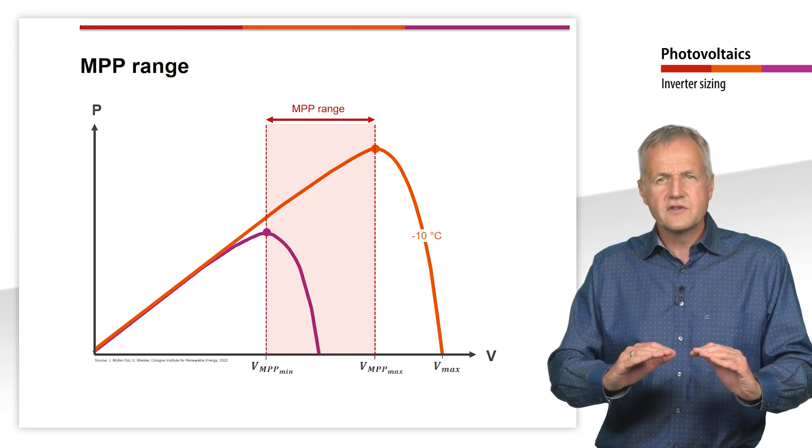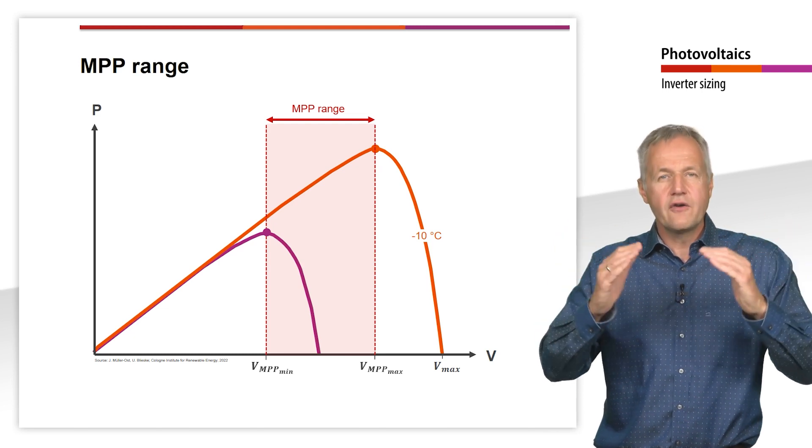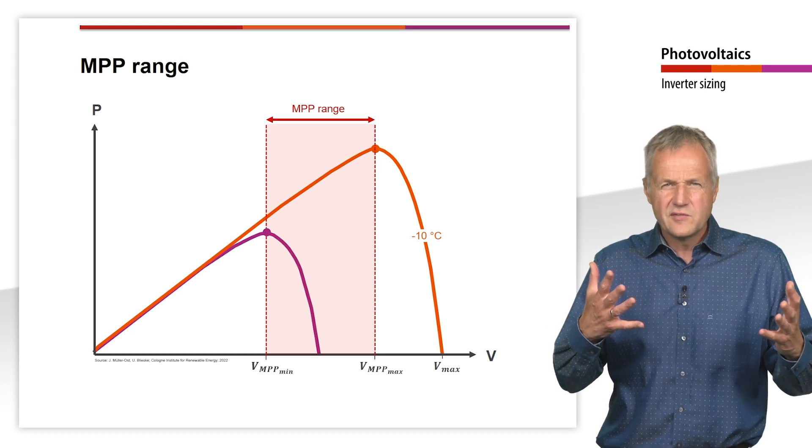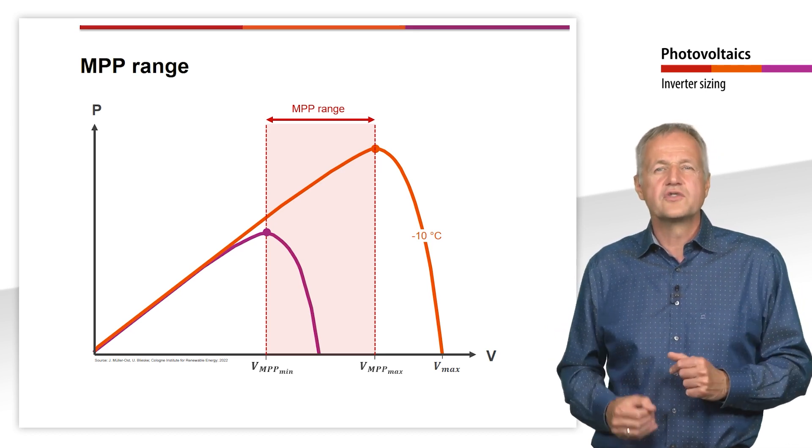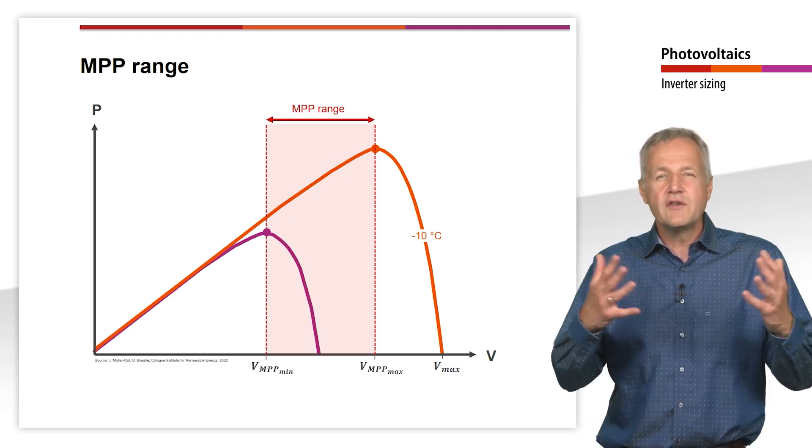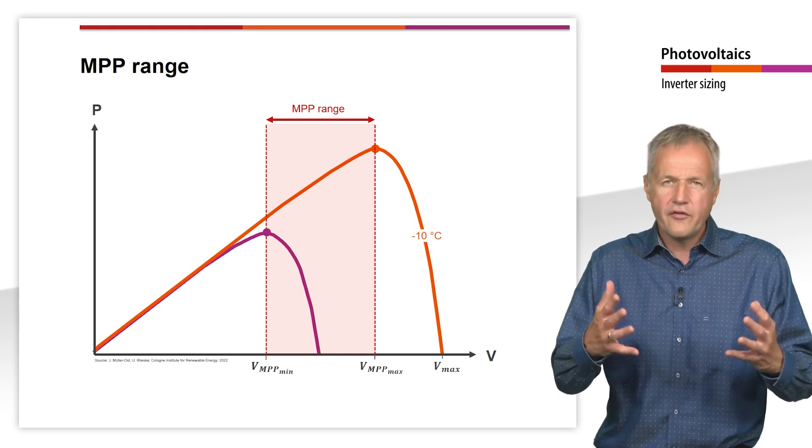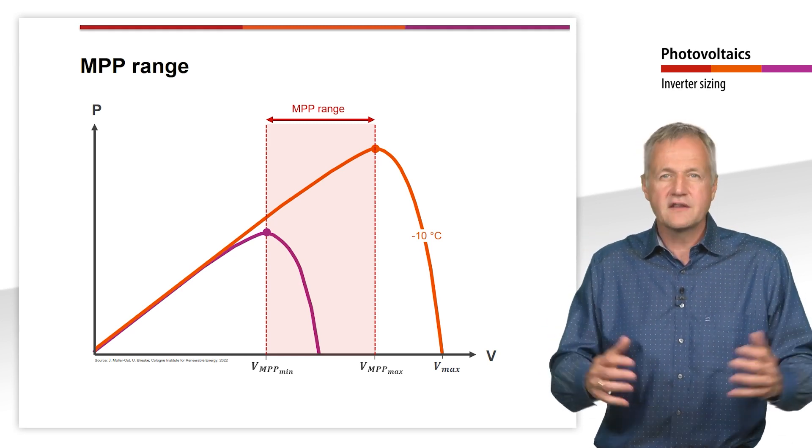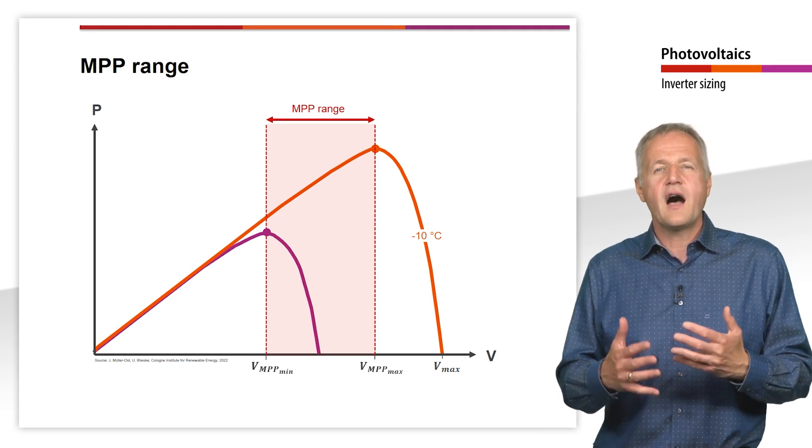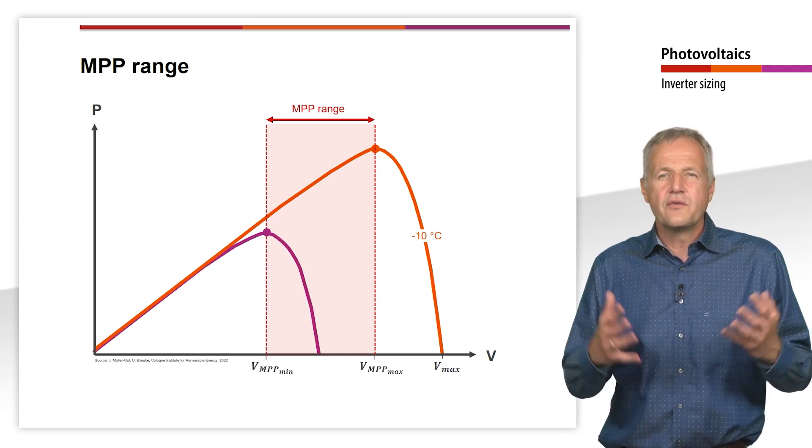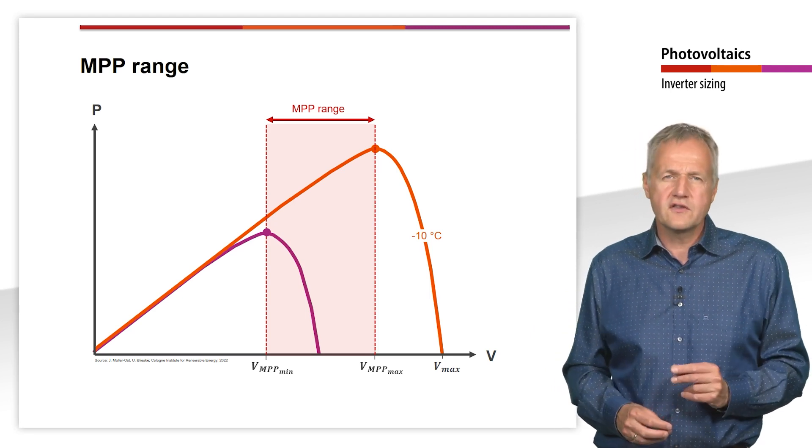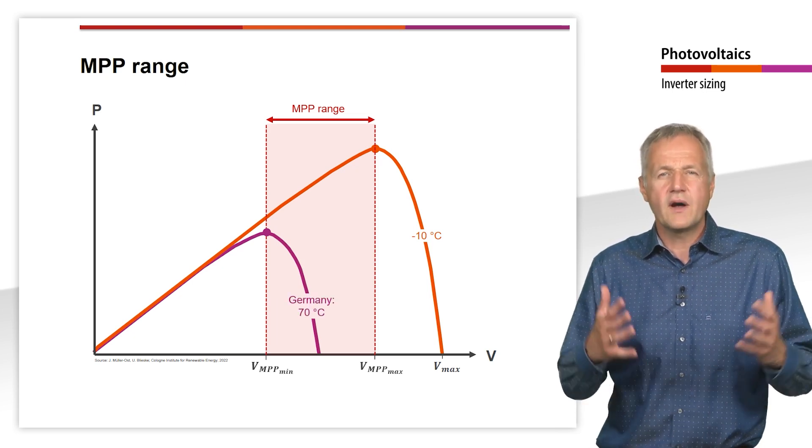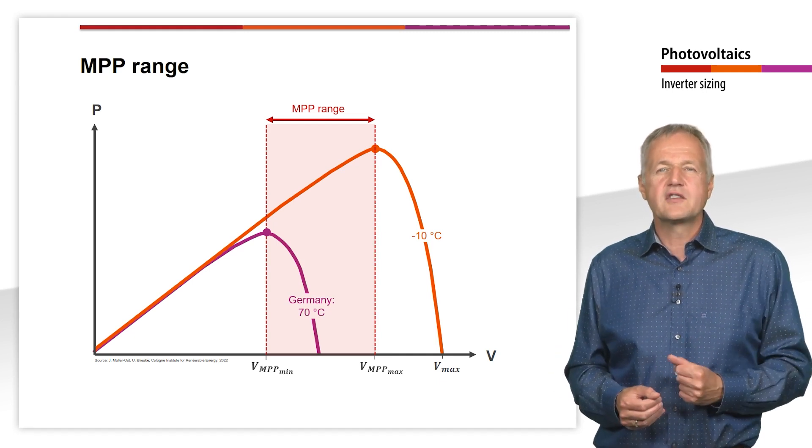This occurs in exactly the opposite case to the situation just considered. The smallest voltage results at very high temperatures with simultaneously very low irradiance. The highest module temperature to be expected also depends on the location, of course. For systems in Germany, 70 degrees Celsius are assumed, which can realistically be reached, especially in poorly ventilated roof-mounted or in-roof systems. However, this maximum temperature will almost never occur together with a very low irradiance since the high module temperature is caused by high direct irradiance. In addition, the irradiance has only a comparatively small influence on the voltage. Therefore, we assume a module temperature of 70 degrees Celsius and an irradiance of 1000 W per square meter for the calculation of the maximum MPP voltage.